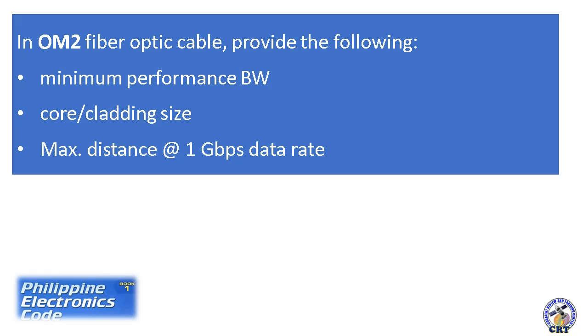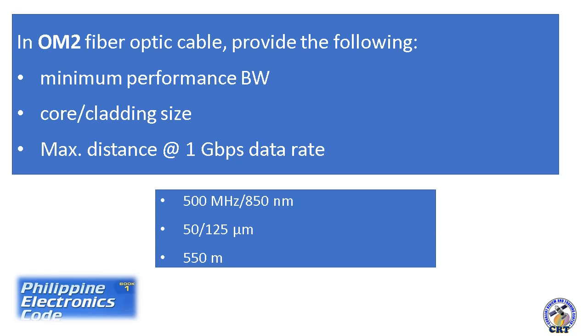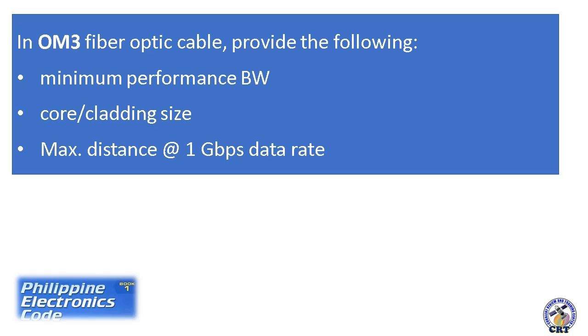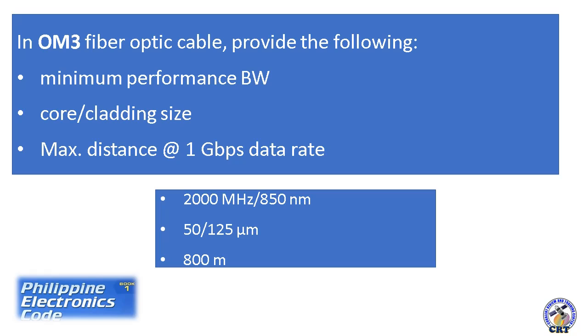In OM2 fiber optic cable, it provides the following. Minimum performance bandwidth, it is 500 megahertz for 850 nanometer wavelength. Core cladding size, 50/125 micrometer. And then for the maximum distance at 1 Gbps data rate, it is 550 meters. In OM3 fiber optic cable, it provides the following. Minimum performance bandwidth, it is 2000 MHz with 850 nanometer wavelength. Core cladding size, it is 50/125 micrometer. And the maximum distance at 1 Gbps data rate is 800 meters.